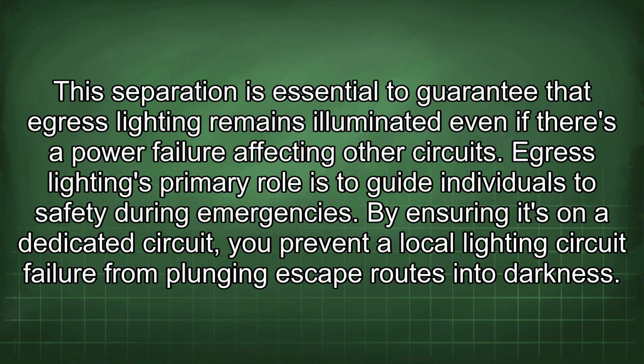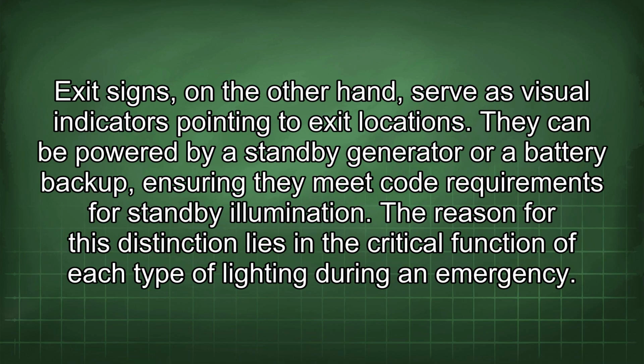Egress lighting's primary role is to guide individuals to safety during emergencies. By ensuring it's on a dedicated circuit, you prevent a local lighting circuit failure from plunging escape routes into darkness. Exit signs, on the other hand, serve as visual indicators pointing to exit locations. They can be powered by a standby generator or a battery backup, ensuring they meet code requirements for standby illumination.